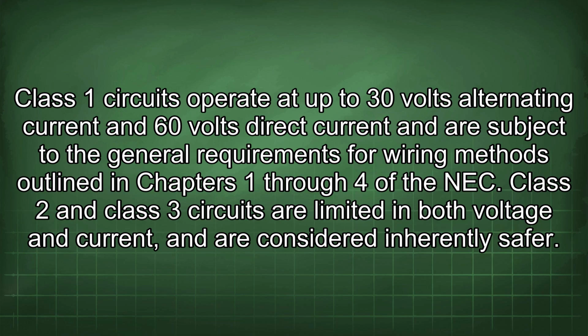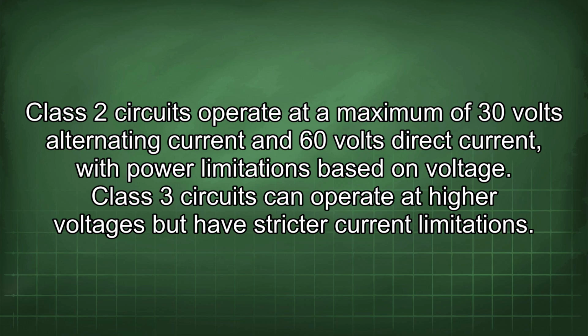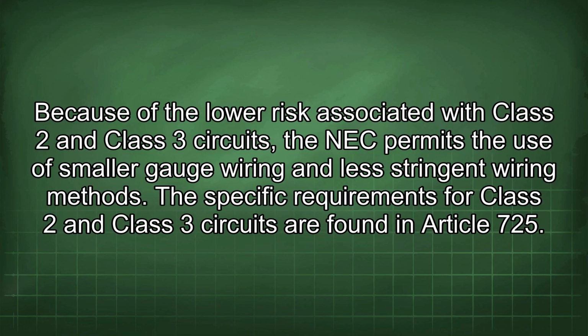Class 2 and Class 3 circuits are limited in both voltage and current and are considered inherently safer. Class 2 circuits operate at a maximum of 30 volts alternating current and 60 volts direct current with power limitations based on voltage. Class 3 circuits can operate at higher voltages but have stricter current limitations. Because of the low risk associated with Class 2 and Class 3 circuits, the NEC permits the use of smaller gauge wiring and less stringent wiring methods. The specific requirements for Class 2 and Class 3 circuits are found in Article 725.